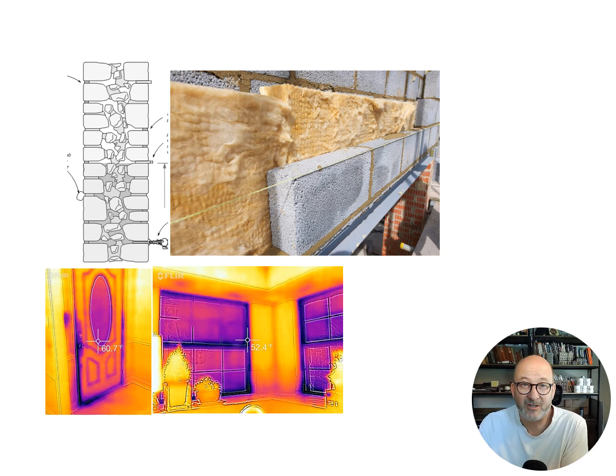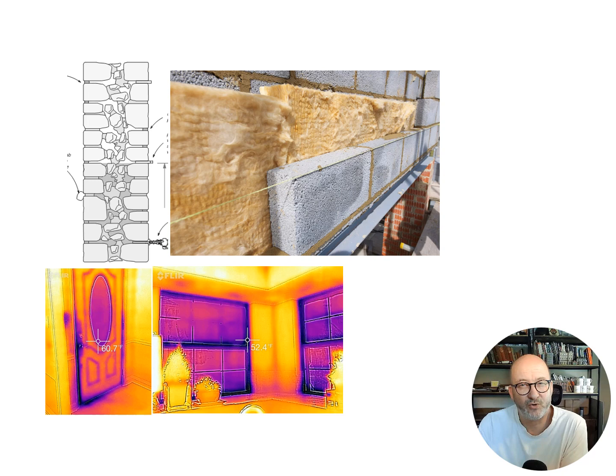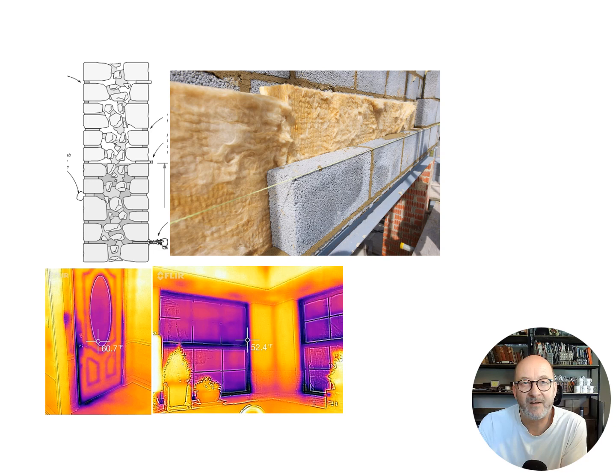Thirdly, condensation models assume that environmental conditions — temperature, moisture, wind, and air pressure — are constant or frozen, but actually conditions constantly change inside and outside buildings. Cold spots occur around windows and doors where lapses or omissions of insulation have occurred, and at thermal short circuits such as lintels and cold bridging. These are all places where problematic condensation is likely to occur in isolation. Furthermore, the prediction of wall condensation does not necessarily indicate it will actually be a problem — the length and severity of winter and the ability of building materials to safely store and later expel moisture are important factors.